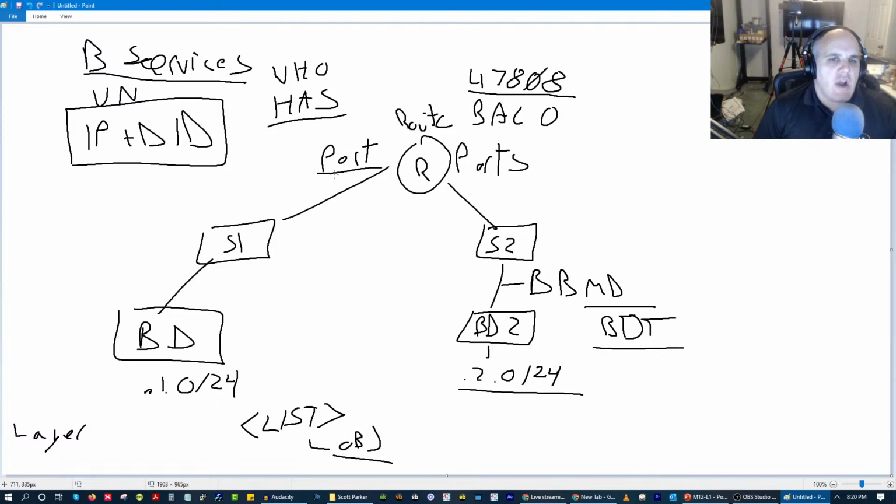Honestly, you're more at risk of having someone hang a 4K camera off of a BACnet IP device that has multiple ports, and then that AV traffic overwhelming your trunk ports than you will ever be of your BACnet traffic overwhelming.